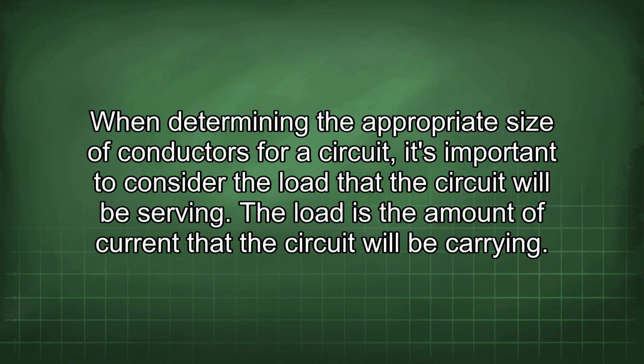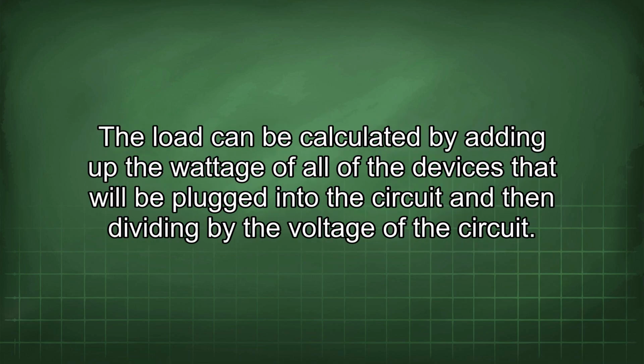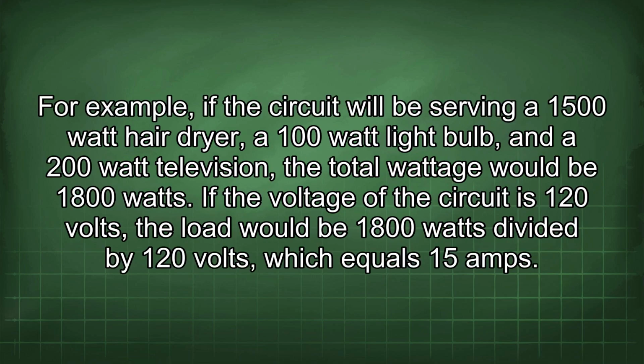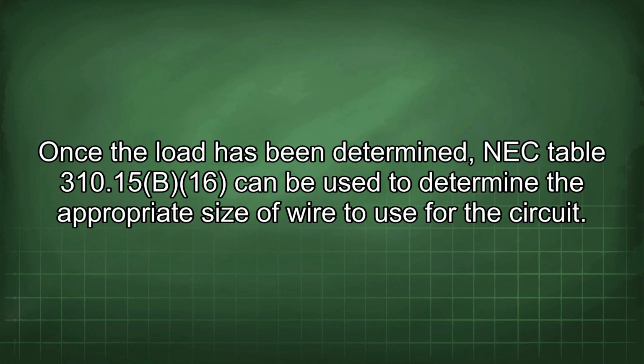When determining the appropriate size of conductors for a circuit, it's important to consider the load that the circuit will be serving. The load is the amount of current that the circuit will be carrying. The load can be calculated by adding up the wattage of all of the devices that will be plugged into the circuit and then dividing by the voltage of the circuit. For example, if the circuit will be serving a 1500 watt hairdryer, a 100 watt light bulb, and a 200 watt television, the total wattage would be 1800 watts. If the voltage of the circuit is 120 volts, the load would be 1800 watts divided by 120 volts, which equals 15 amps. Once the load has been determined, NEC Table 310.15(B)(16) can be used to determine the appropriate size of wire to use for the circuit.